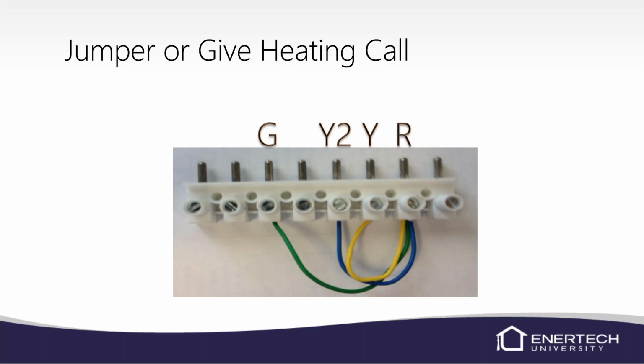Basically, we just use this so we don't have to worry about running up and down the stairs. It never fails. You give the thermostat a call and you wait down at the unit for what seems like an eternity, and then about the time you walk up to the thermostat, it kicks back on. So sometimes it's just easier to jumper it out, pull the test pin or flip the test jumper and speed up the time delays, and not have a time delay from the thermostat as well. So you basically just need a G, a Y, Y2 if you've got a two-stage unit, and the R, and we'll just jumper all those together. If you've got a water-to-water unit, you don't need the G, obviously. There is no fan on a water-to-water unit.